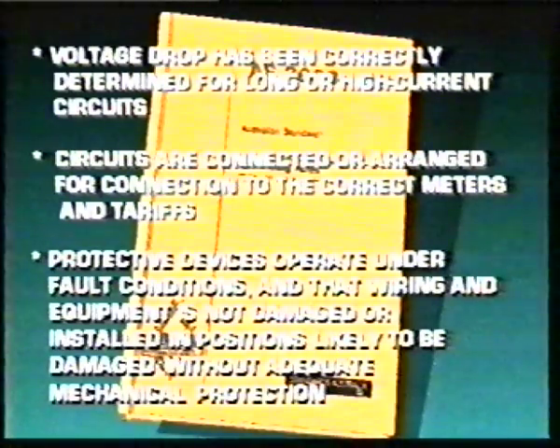Voltage drop has been correctly determined for long or high current circuits. Circuits are connected or arranged for connection to the correct meters and tariffs. Protective devices, particularly the residual current type, operate under fault conditions. And that wiring and equipment is not damaged or installed in positions likely to be damaged without adequate mechanical protection.